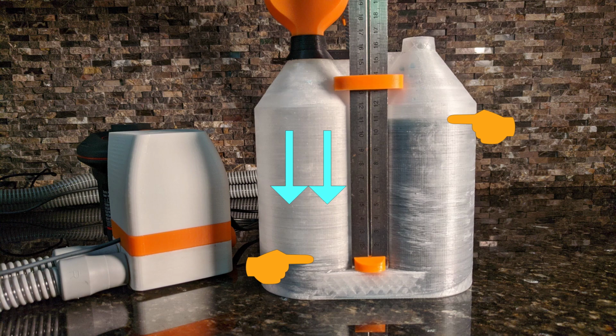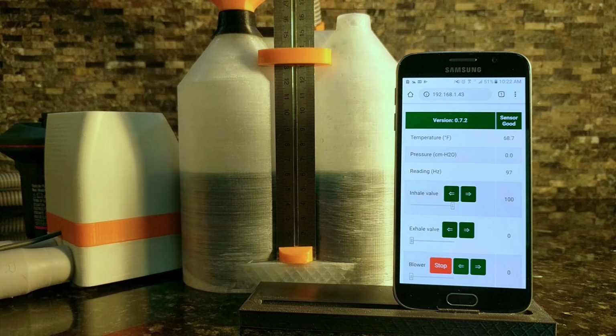This test lung was 3D printed with one extra key feature. The cross-sectional area of each of the cylinders is 50 square centimeters. Thus, when the water is 10 centimeters high, as in this case, there is 500 milliliters of volume, our specified pressure and volume. At the moment, the user interface is rather simplistic, but over the coming weeks, nice real-time graphs that the industry expects and friendly configuration screens will be added. This particular screen shows some key values, in a development sense that is. The test will be activated by the tablet off screen, but you will be able to see the activities of the InqVent on this smartphone.